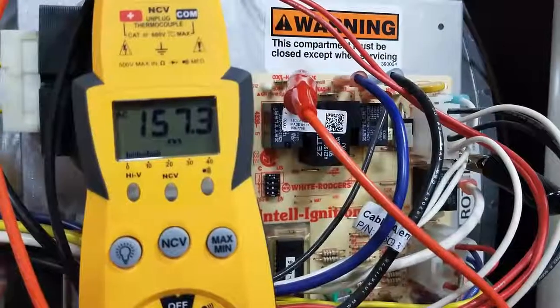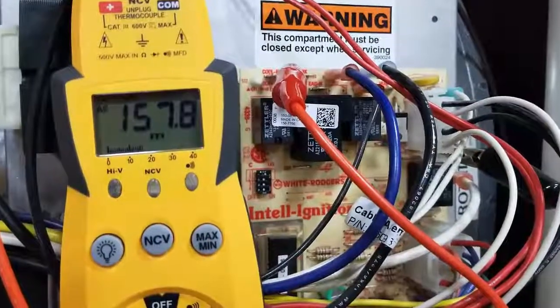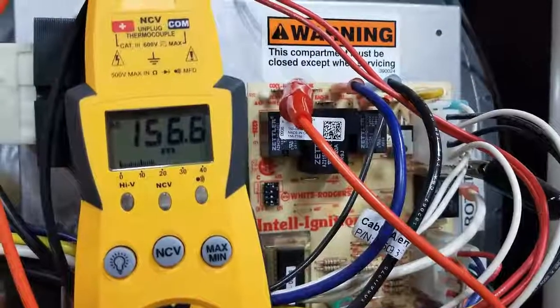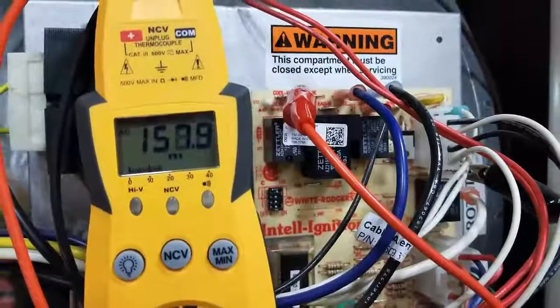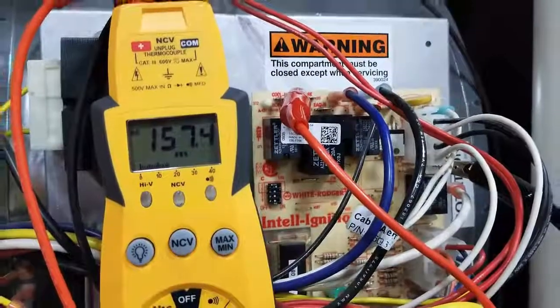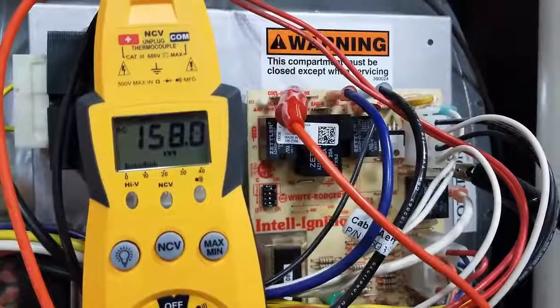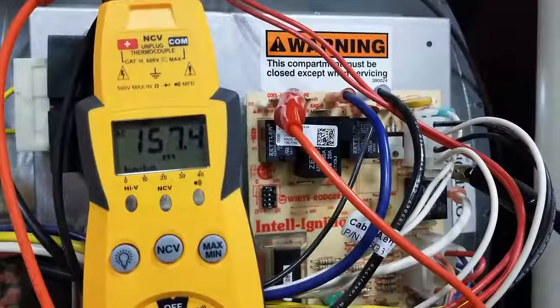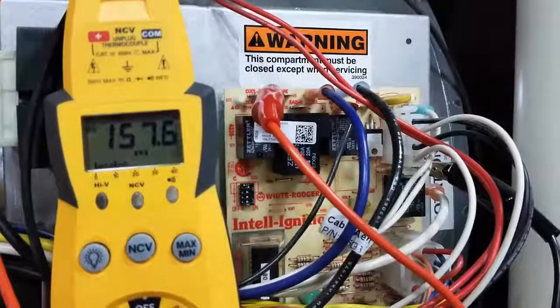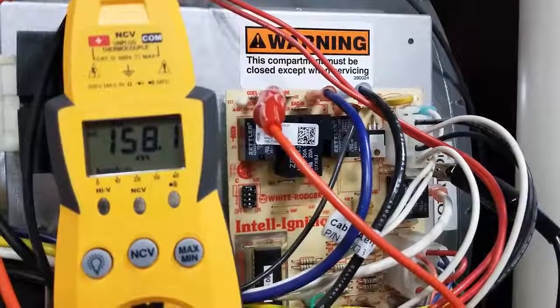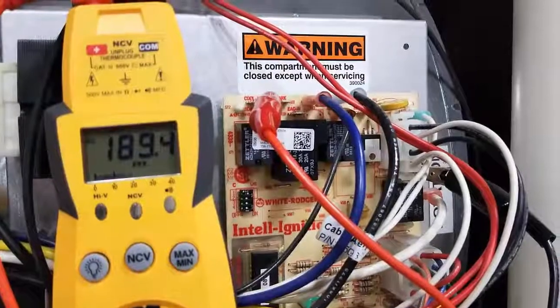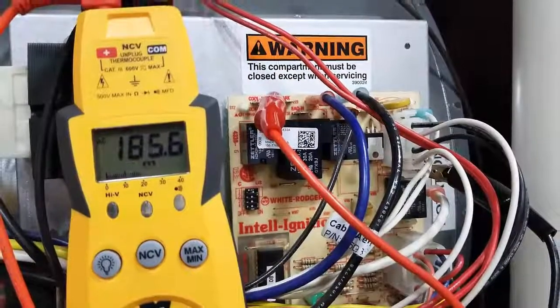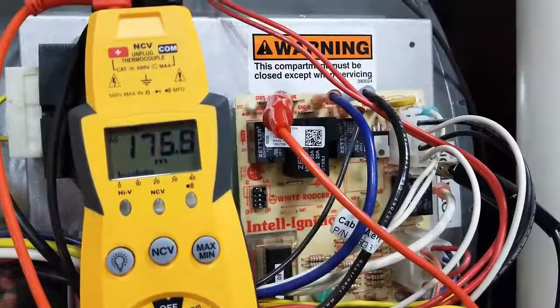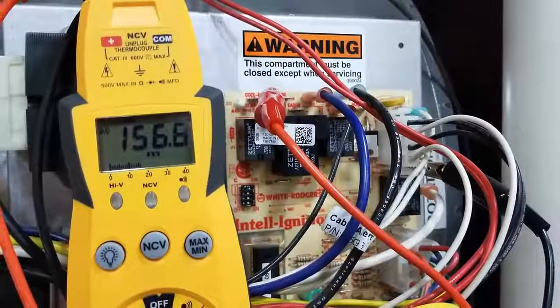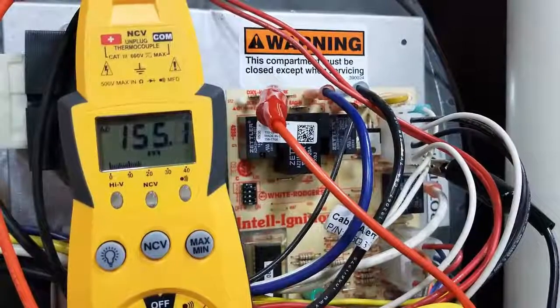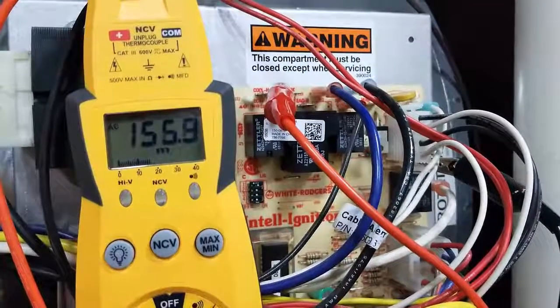Again, what we're reading here is just millivolts. It's just feedback through the system. You can't see it on film, but the igniter has started to glow. So it shouldn't be too much longer here, and if everything's working correctly, we'll see 120 volts at the circuit board, which, if the fan wires were plugged into it, means we'd get 120 volts to the fan. Okay, burner's just fired. So again, we've got about another 20 to 30 seconds before the blower should start.